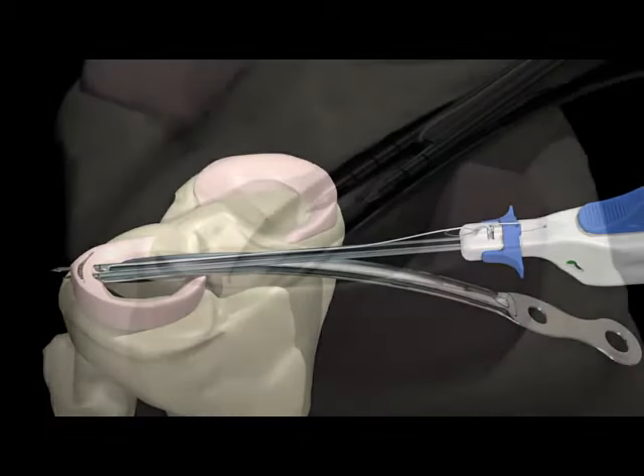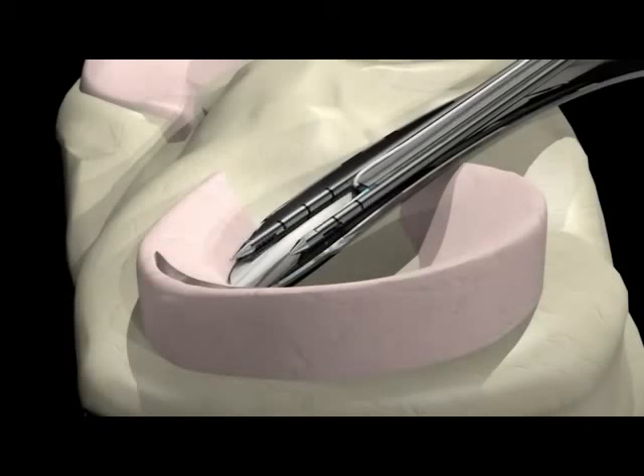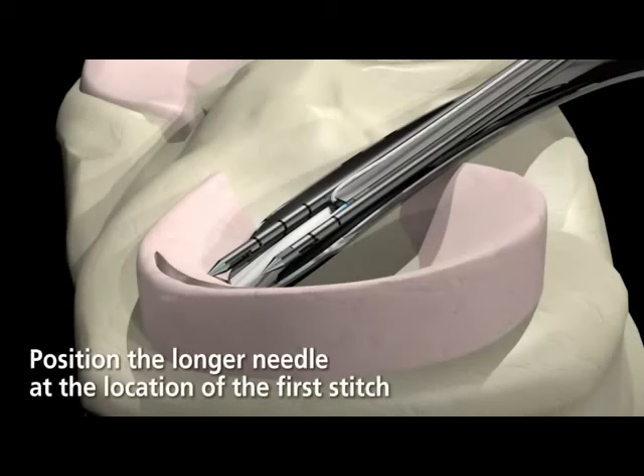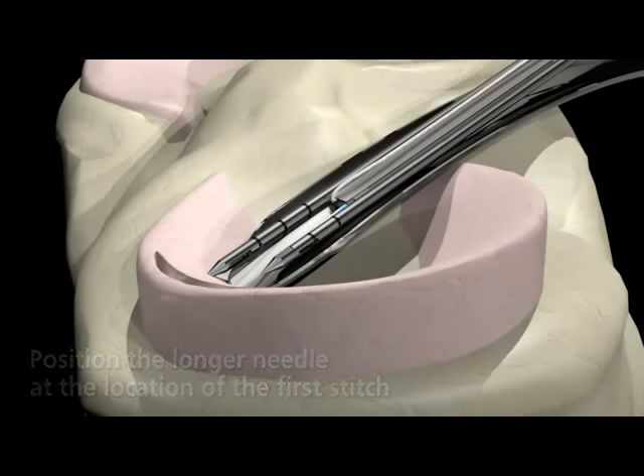Carefully advance the AS meniscal repair device against the meniscus at the predetermined point of penetration at the repair site. The alignment of the needles on the device is critical; they are not designed or intended to manipulate or position tissue. Do not subject the device to forces that may misalign or bend the needles, as doing so may affect their ability to place and/or pass the suture.